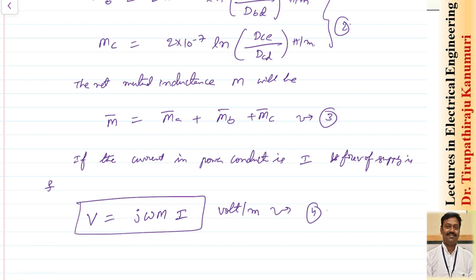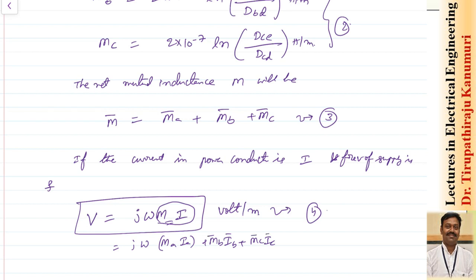Because of this induced voltage, current starts passing in the communication line, distorting the signal. The magnitude of flux linkages and induced EMF mainly depends on whether the current is balanced or unbalanced. For unbalanced currents the expression becomes V = jω(M_A×I_A + M_B×I_B + M_C×I_C). If all currents are equal, it simplifies to V = jωMI.